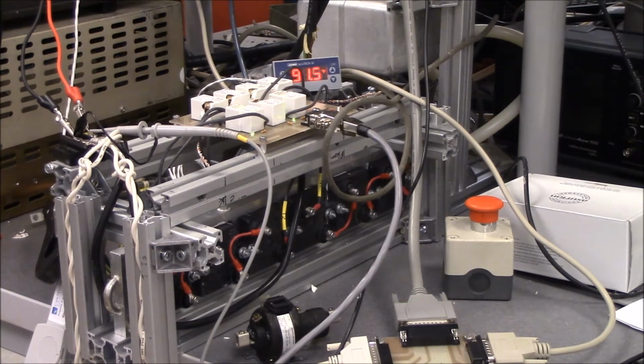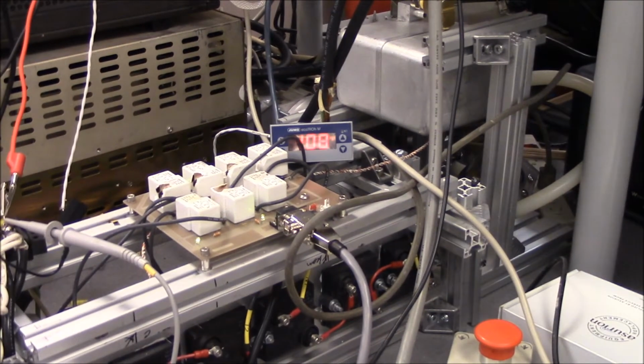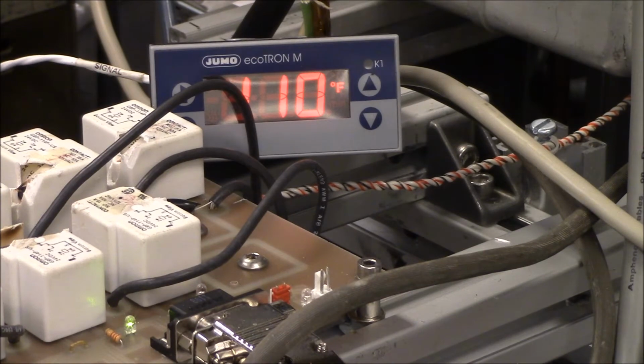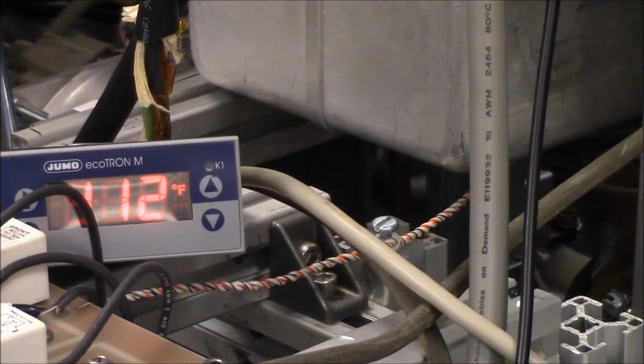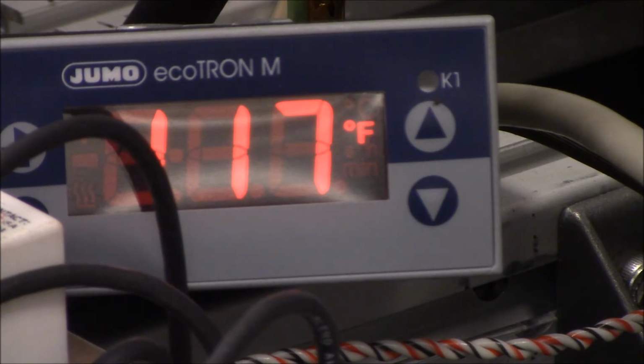And as the temperature goes up, a fan controller will adjust the airflow from our fan. There is a water wheel to make sure that the pump is flowing correctly and gives us information regarding water flow. That pictured center is the radiator. And as you can hear, as the temperature still climbs, the fan grows louder. We have automatic fan control so that when we're operating at lower ranges, we aren't deafened by the fan, whose maximum air movement is 460 cubic feet a minute and is quite loud. It pulls 2 amps at 24 volts. The maximum steady state temperature of the system is 160 Fahrenheit.